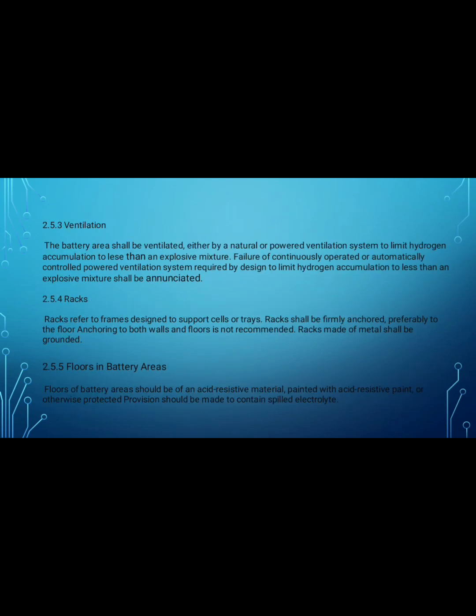2.5.3 Ventilation. The battery area shall be ventilated either by natural or powered ventilation system to limit hydrogen accumulation to less than an explosive mixture. Failure of continuously operated or automatically controlled power ventilation system required by design to limit hydrogen accumulation to less than an explosive mixture shall be annunciated.